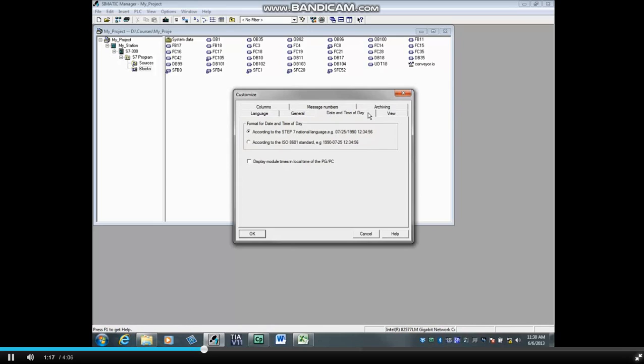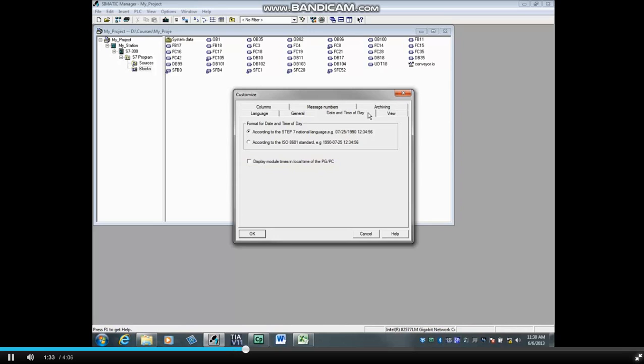Placing a check in the box Display Module Times in Local Time of the PG/PC will convert diagnostic message timestamps to the local computer's time. This box should only be checked if the PLC is set to Universal Time or UTC.